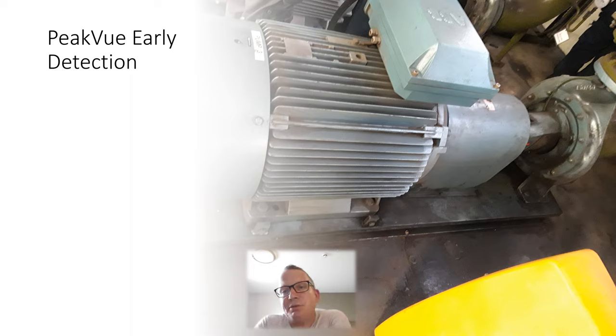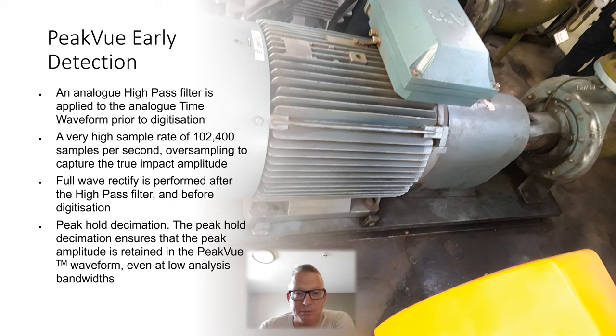Now Emerson has got some unique processes in the way the technology works, which is unique to them, which makes it why it works so well. Very basically, we've got an analog high pass filter applied to the analog time waveform, prior to digitisation. The bit which sets them apart is this bit here, where it actually samples at a rate of 102,400.